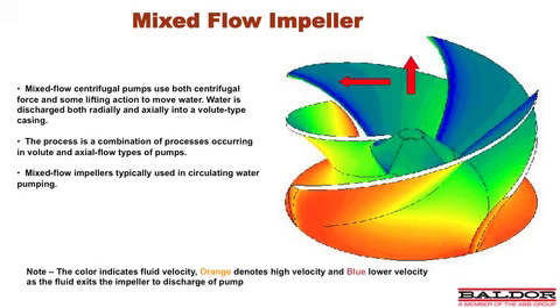And the image on your right is showing a basic 3D model of a typical mixed flow impeller. Mixed flow impellers utilize both centrifugal force and lifting force action to move the water. And you can see by the horizontal arrow and the vertical arrow, we're showing where the water is discharged both radially and axially into the volute casing. The orange coloring on the impeller denotes high velocity fluid flow, and the blue is showing lower velocity at the exit of the impeller to the discharge of the pump.